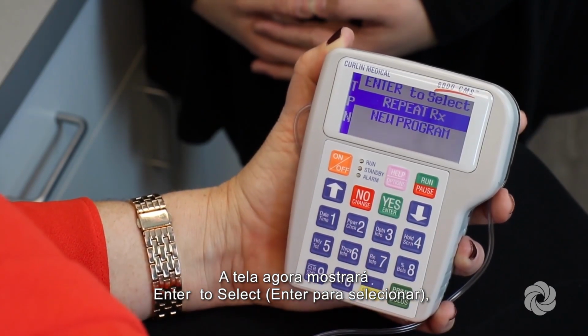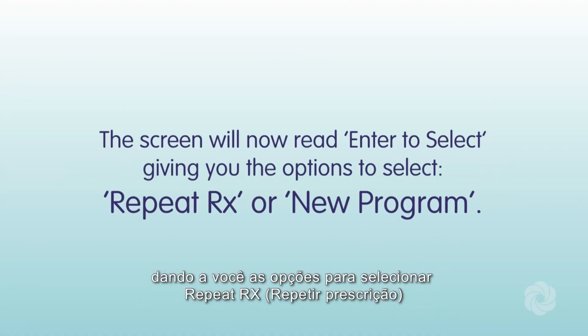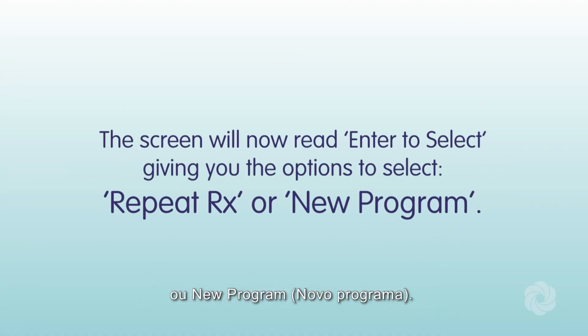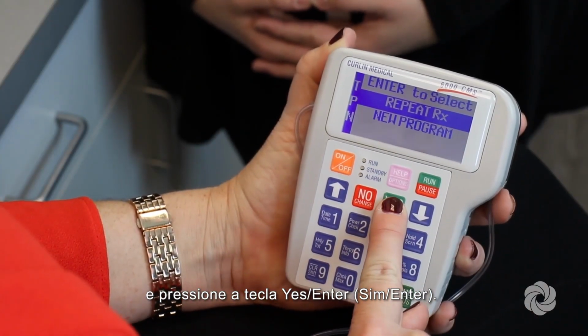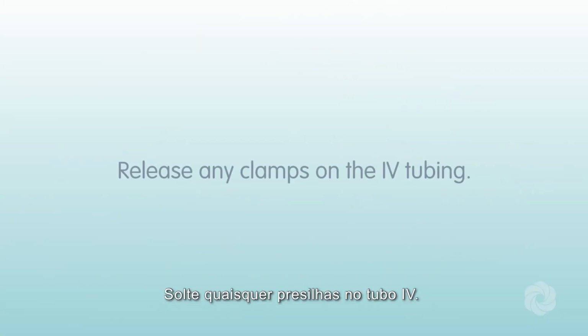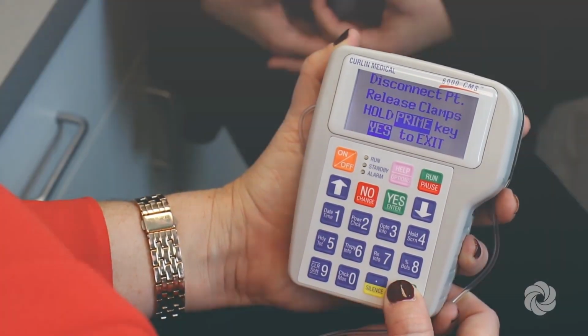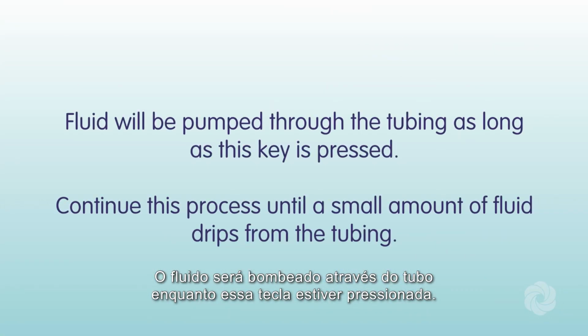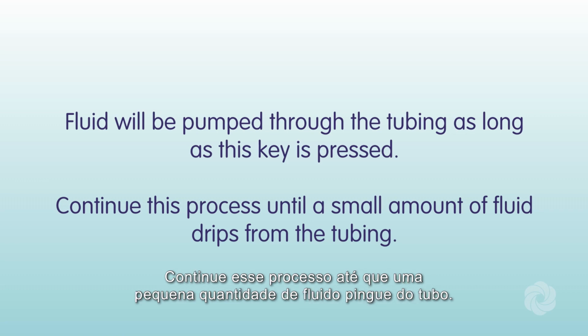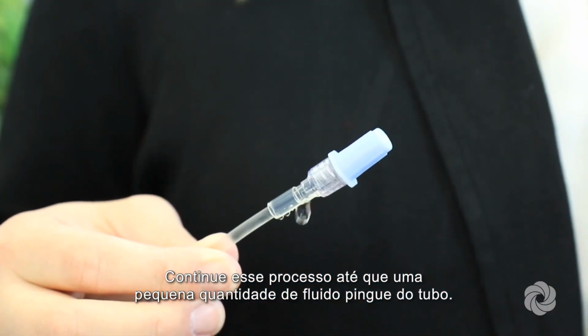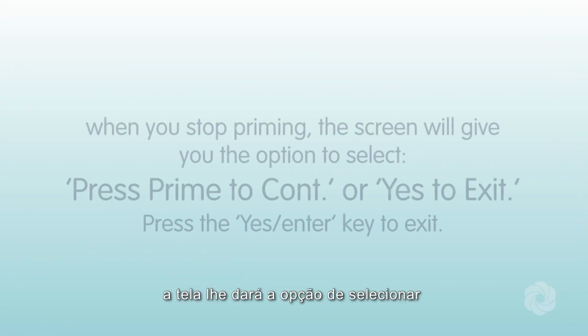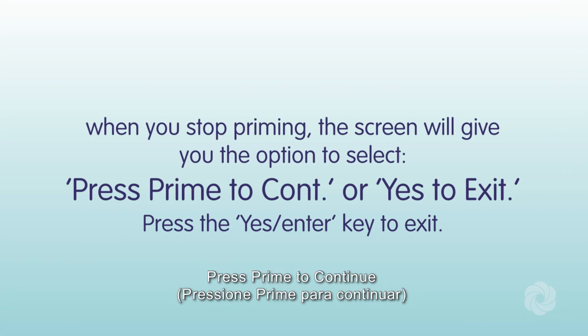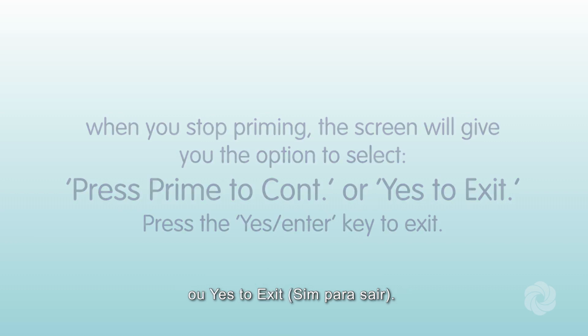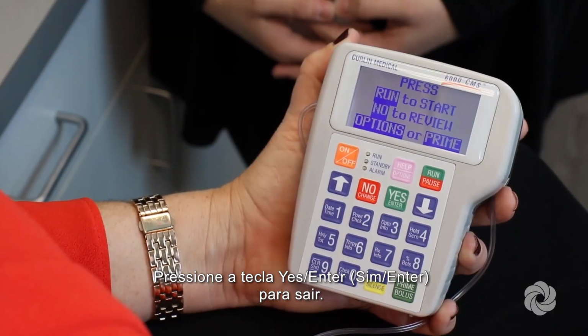The screen will now read Enter to Select, giving you the option to select Repeat RX or New Program. Using the up-down arrows, highlight Repeat RX, then press the Yes Enter key. Release any clamps on the IV tubing. Press and hold the prime bolus key. Fluid will be pumped through the tubing as long as this key is pressed. Continue this process until a small amount of fluid drips from the tubing. Lastly, when you stop priming, the screen will give you the option to select Press Prime to continue or Yes to exit. Press the Yes Enter key to exit.